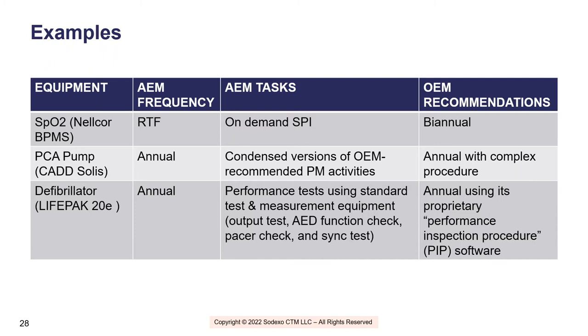PCA pumps, like a CADD Solis, there's an annual requirement. We perform those annual checks. The only difference is that we consolidate where they have 8 to 10 steps to get to run rate on a volume. We just do one.